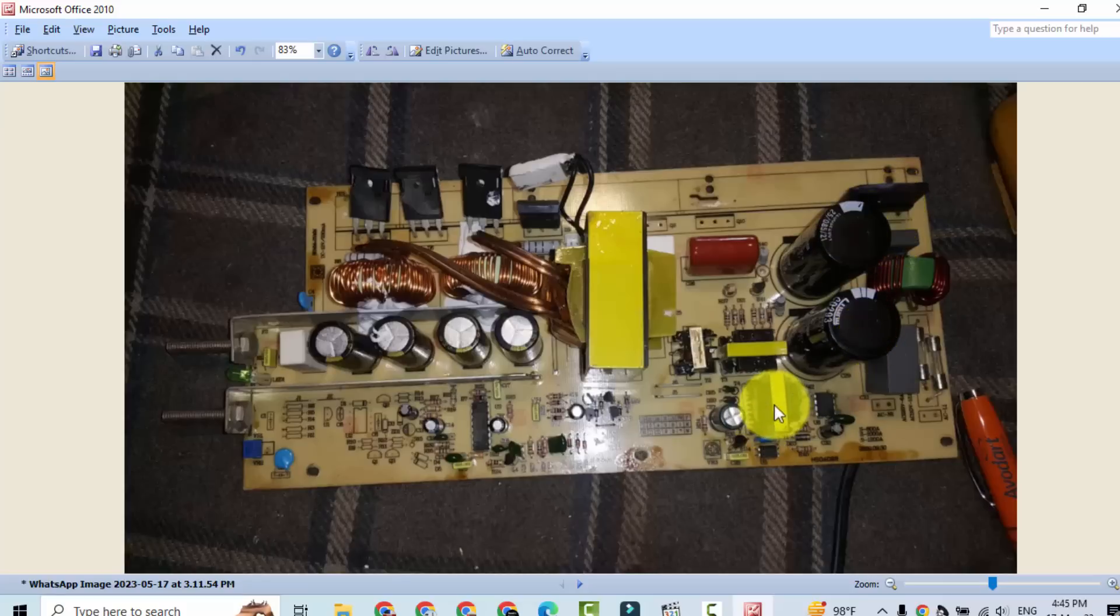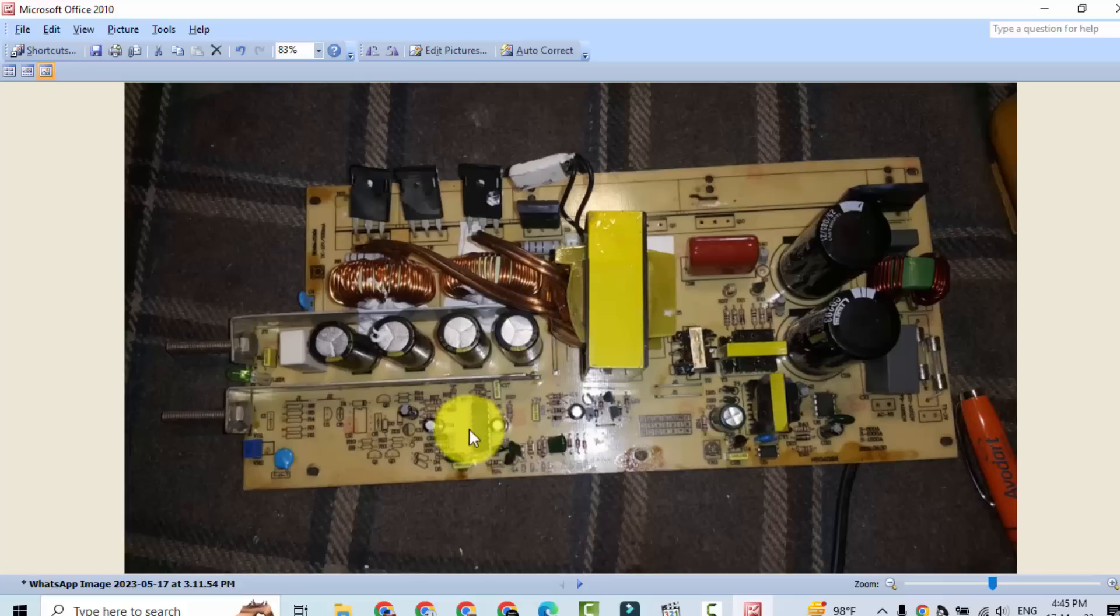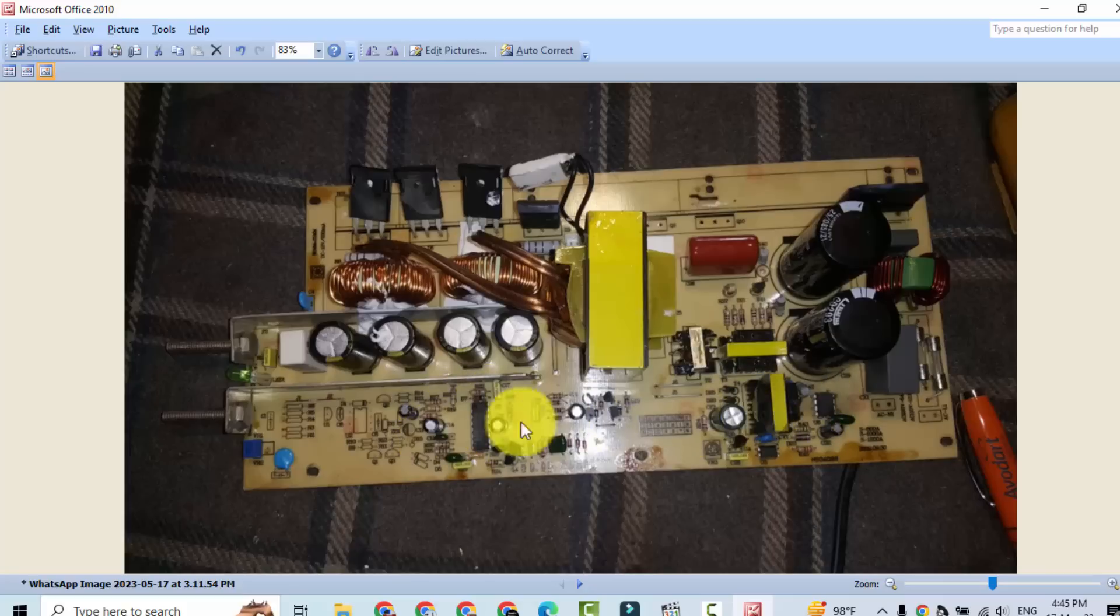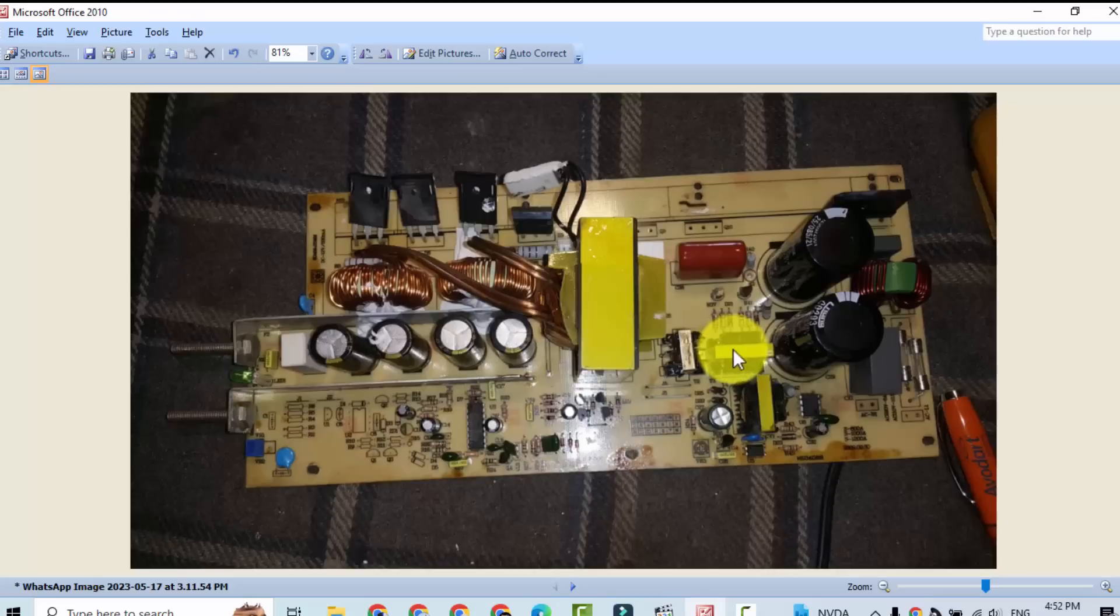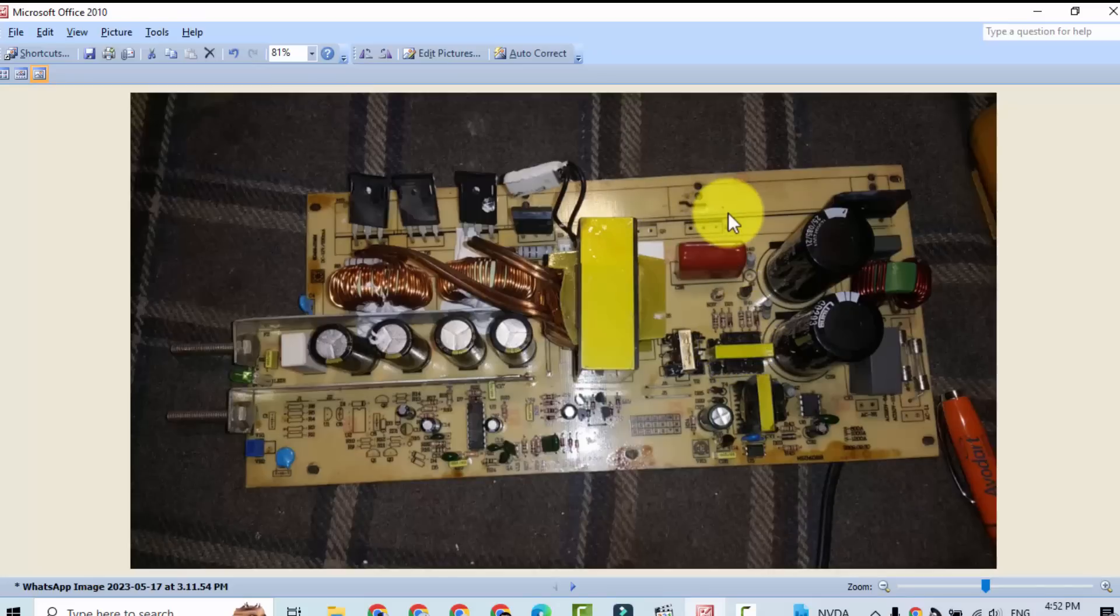This portion is standby section. It will provide power to this IC first. This section will start, after that it will start. When it will start, this IC will drive this signal driver stage and it will drive this pulse transformer. This pulse transformer will drive IGBTs behind this board.